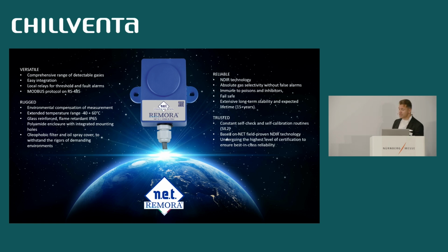Great long-term stability. The sensor has internal self-check and self-calibration routines, and the optical nature of the gas detection technology guarantees an expected lifetime to exceed 15 years. It will undergo the highest level of certification to ensure great reliability. The sensor will be certified to IEC 60335-2-40 Annex LL. It will be certified to SIL 2.